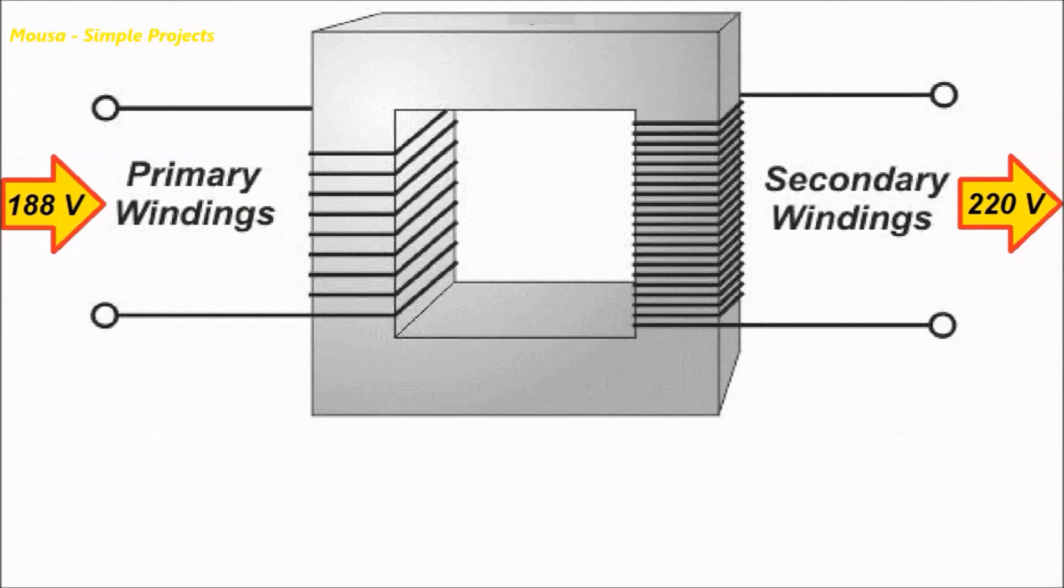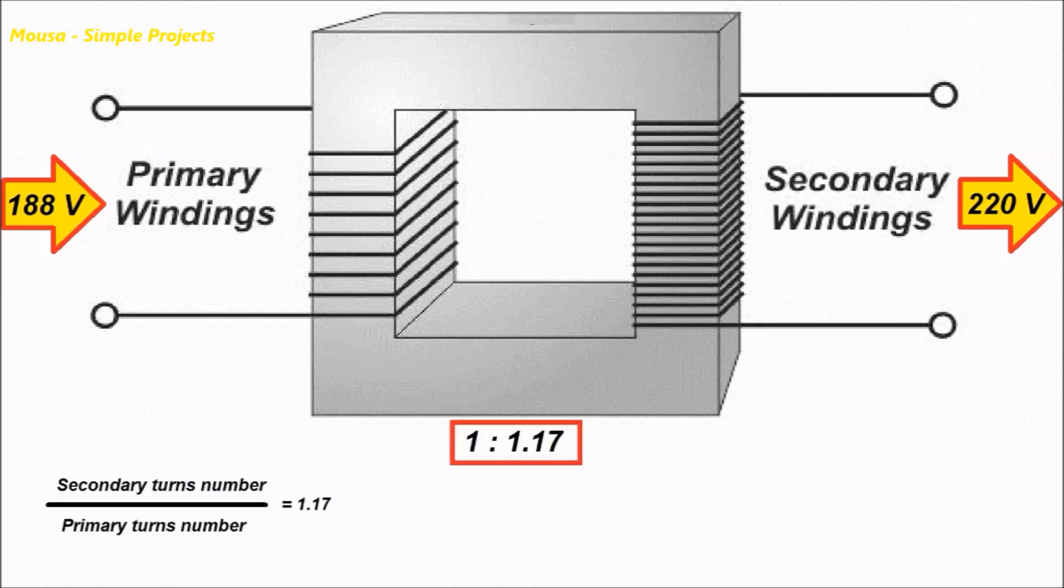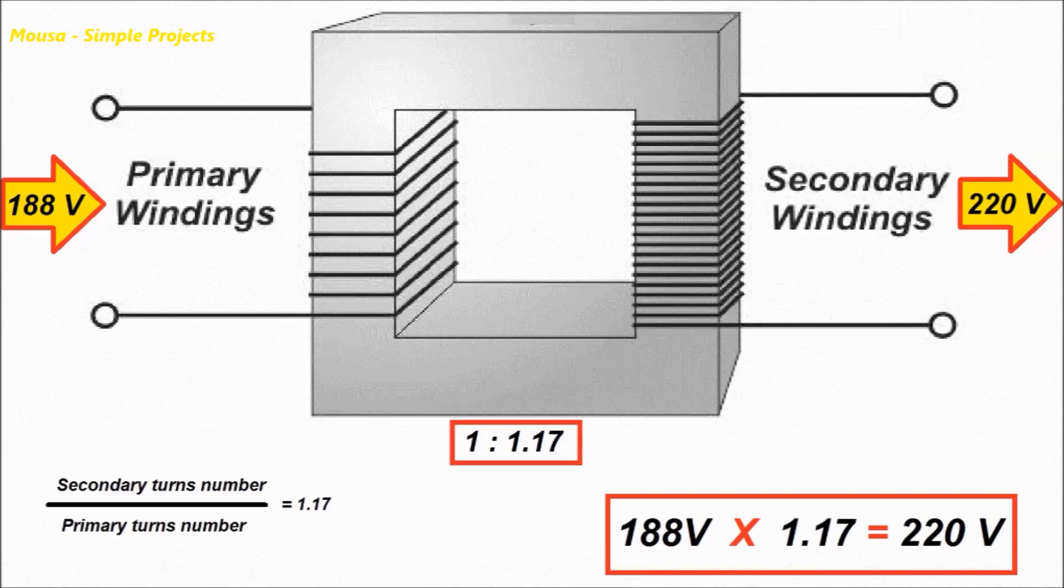To solve this problem simply we can use a transformer. In this case the ratio of the secondary turns number to the primary turns number should be 1.17. That means the 188 volts at the primary side of the transformer multiply by 1.17, so the voltage at the secondary side will be 220 volts.